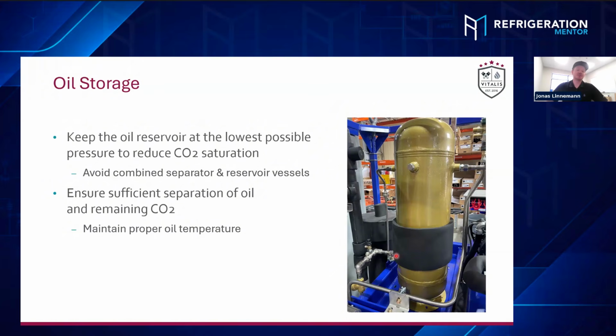You don't want to have it too hot. We have seen that at the very beginning. There's a sweet spot of oil temperature. So we do use a self-regulating oil heater, which is maintaining the oil at about 40 degrees C. That's very important if you have an installation outside, especially in enclosures, and in the wintertime, that would just cool down too much. In regular operation, these heaters are not very often active.